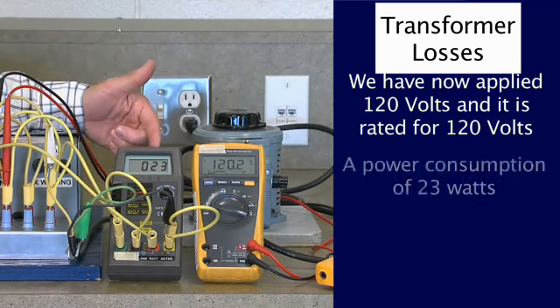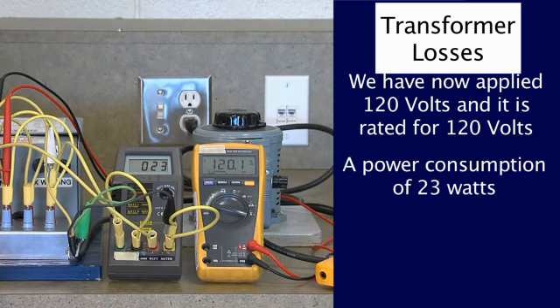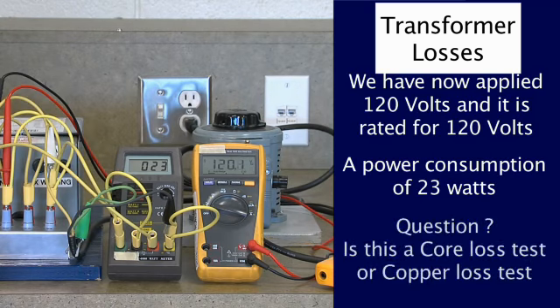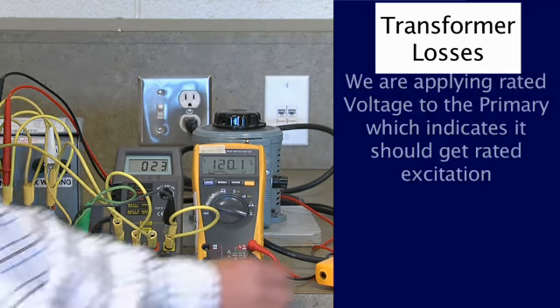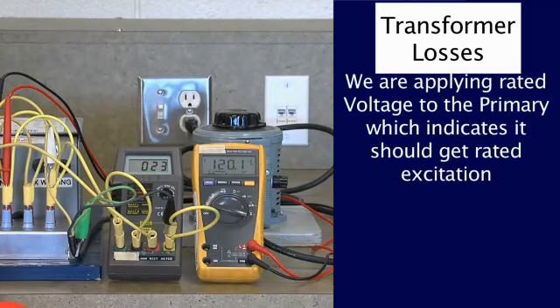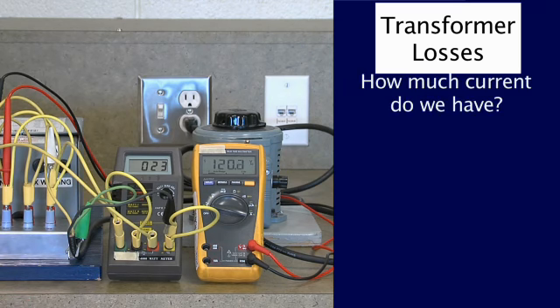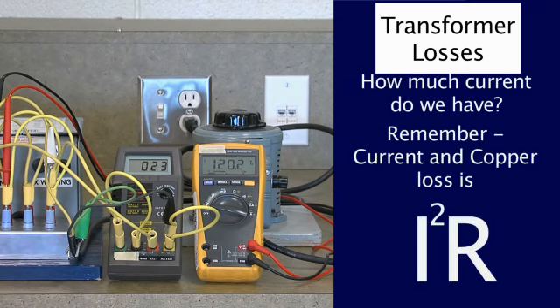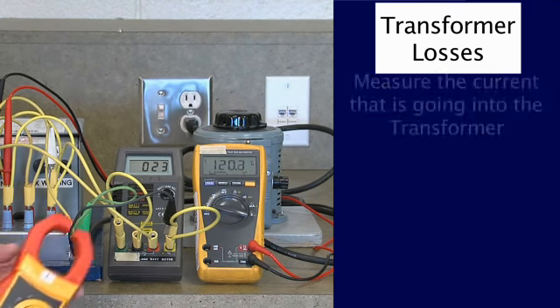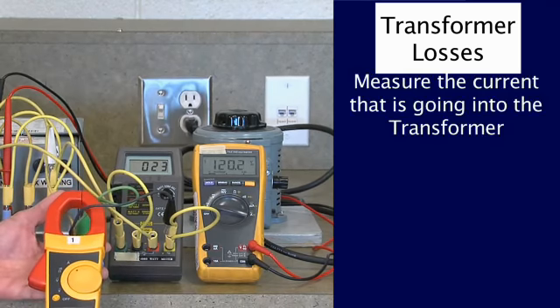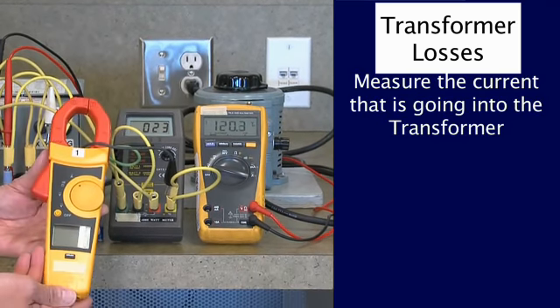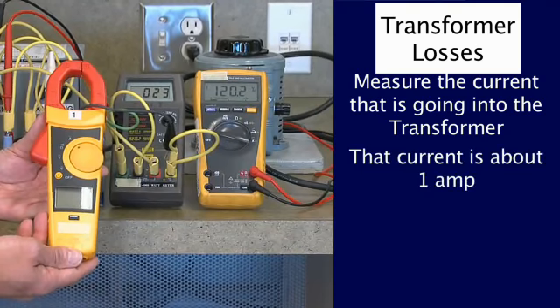I have a power consumption of 23 watts here. Now the question is, is this a core loss test or a copper loss test? Well, I'm applying rated voltage to the primary. That would tell me that I should get rated excitation. But how much current have I got? Remember, current and copper loss is I squared R. So what I'm going to do is measure the current that's going into this transformer. And that current is about 1 amp.